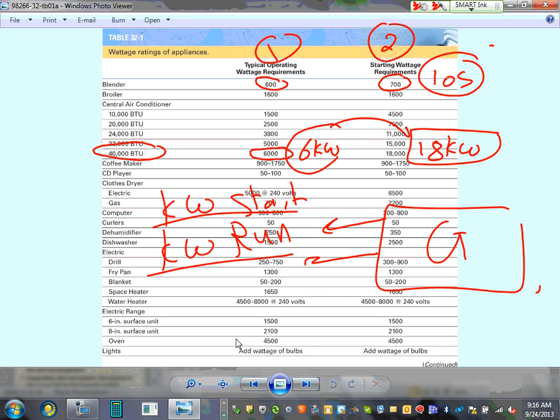What happens, guys, if your generator cannot start the equipment is that it will stall. It just can't start it. It's too heavy. Imagine starting is like lifting things. If you have a heavy thing, you need more oomph just to pick it up, right? After you pick it up, you can run with it, but picking it up, that's the start. Same thing for a generator. To start it typically takes 3 to 6 times more.